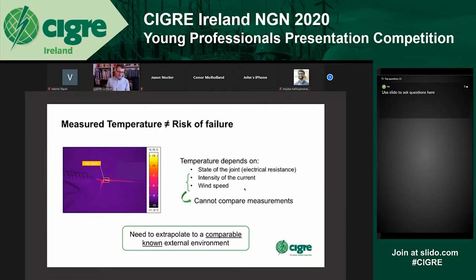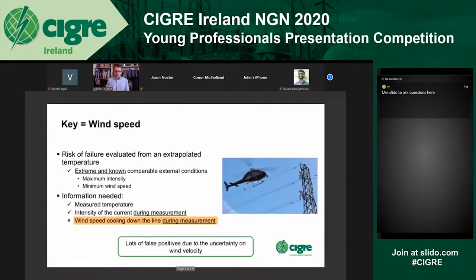It also depends on wind speed—more wind means more cooling. The problem is that for different conditions like intensity or wind speed, you'll measure different temperatures, and you don't know which of those temperatures to use to assess the risk of failure. So you need to extrapolate the measurement to a comparable and known external environment to assess the risk properly, and this is usually what is done.